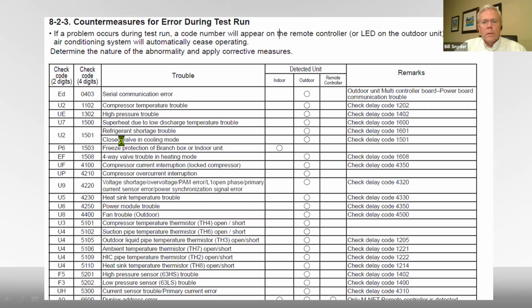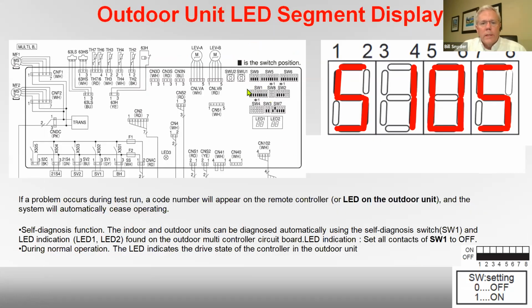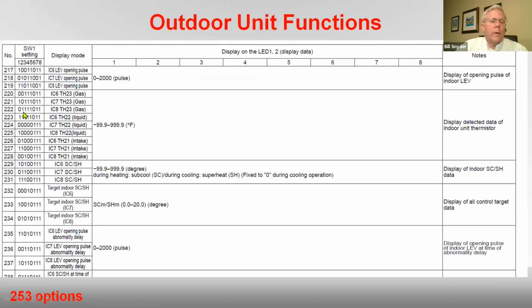Now, let's go back here. Right here, this SW1, these are switches, okay? So we can change this dip switch, SW1, looks like this, 0 meaning off, 1 meaning on. If we go down here to this page and turn them on and off, we can see the pulse of the various LEVs. You can see the liquid temperatures on these thermistors. You can see the LEV pulse rates down here.